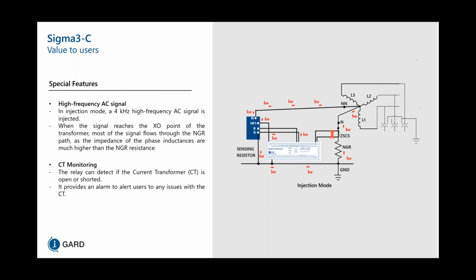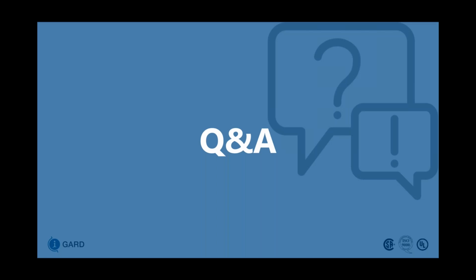So high frequency AC signal is the key feature for Sigma 3C that differentiates us from the competitors in the market currently using a DC based injection. It's a 4 kilohertz high frequency AC signal, and when the signal reaches the XO point of the NGR of the transformer, most of the signal flows through the NGR path as the impedance of the phase inductances is much higher than the NGR resistance. In addition to that, we've also included CT monitoring so that the relay can detect if the current transformer is open or shorted, and it provides an alarm to alert users to any issues with the CT.